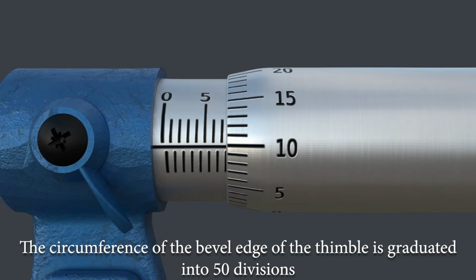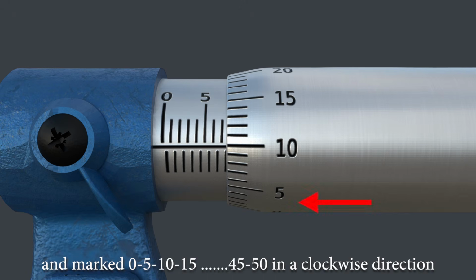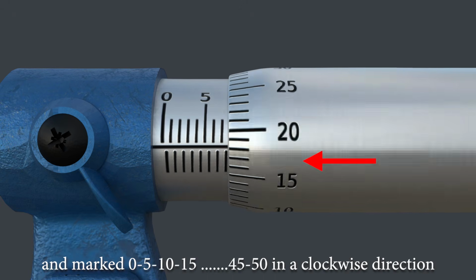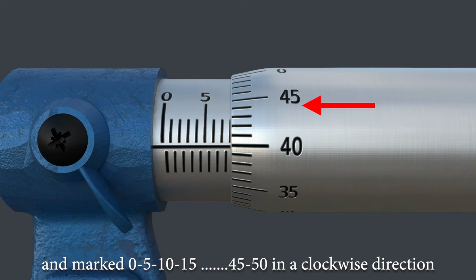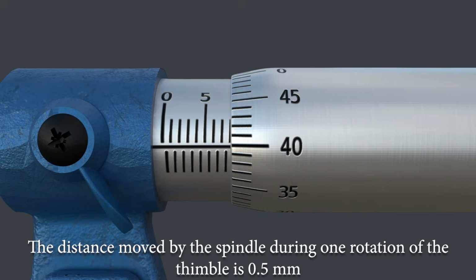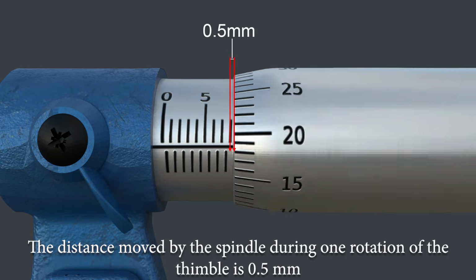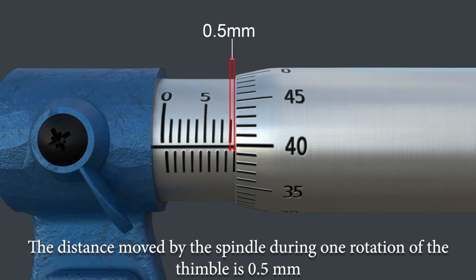The circumference of the bevel edge of the thimble is graduated into 50 divisions and marked 0 to 5 to 10 to 15 and so on till 45 to 50 in a clockwise direction. The distance moved by the spindle during one thimble rotation is 0.5 mm.